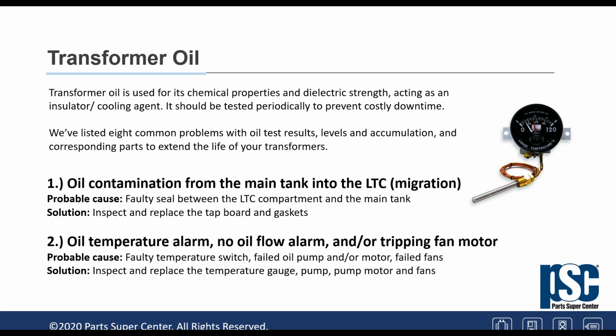So that's the reason why, if the amount of gas in the main tank is not that much, and we got plenty of gas in the LTC, common sense says drain the oil. But in that case, we have to turn the unit off, and we've got to go look at the tap changer.